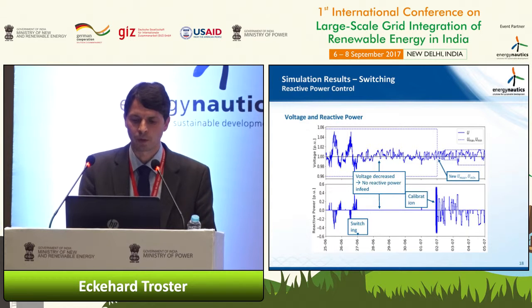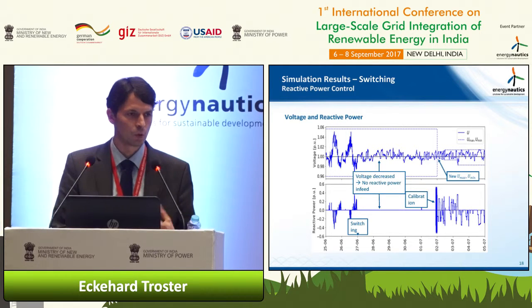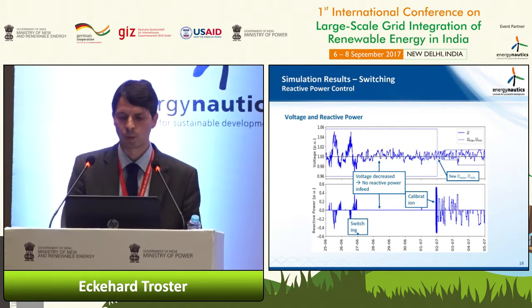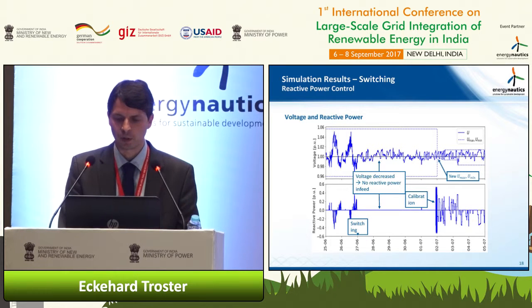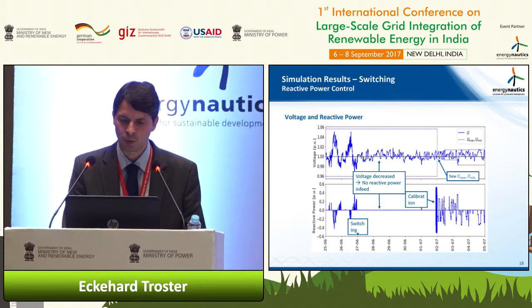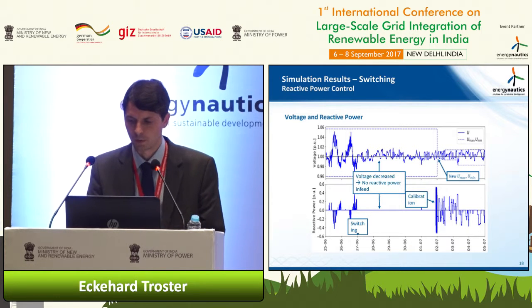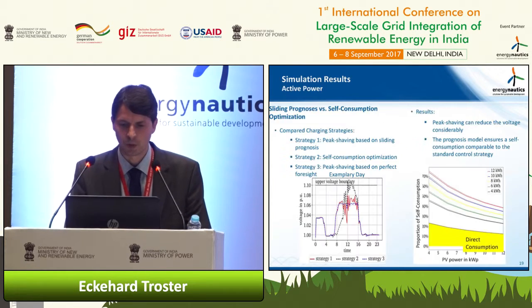So here, on 27 June, there's a switching happening. After that, the voltage is much lower, and my system is not doing any reactive power control anymore. We can determine this, and then we do a calibration as shown here, and from there on, reactive power provision is continued. So that works quite nicely.